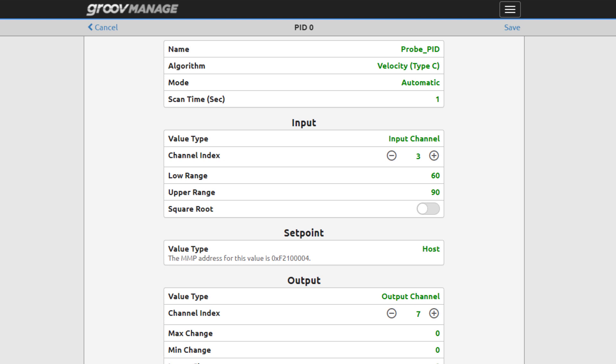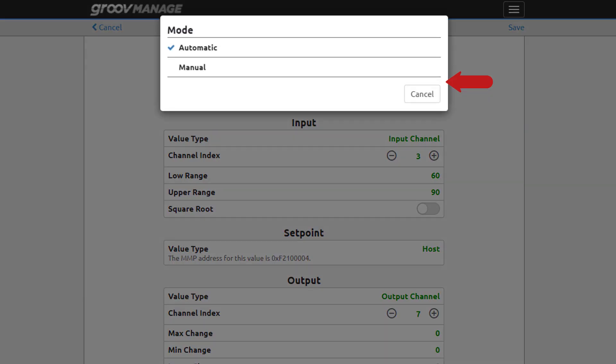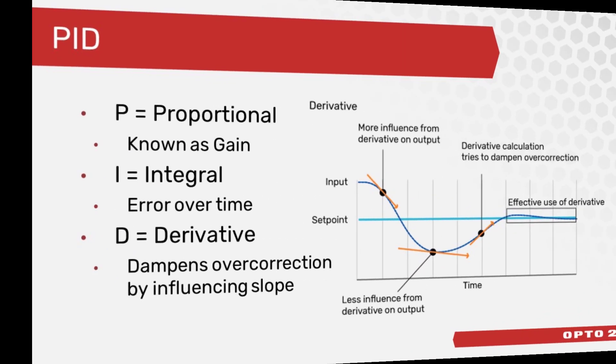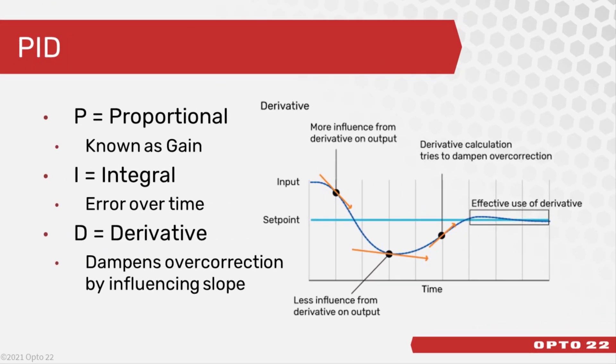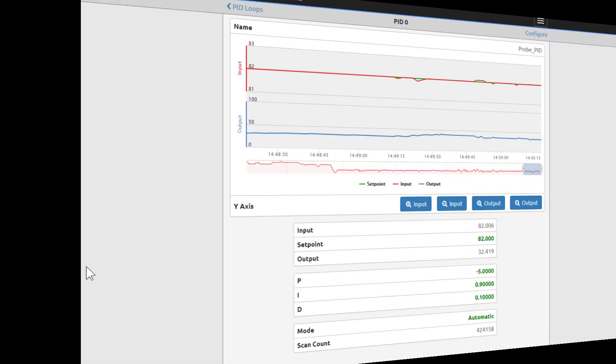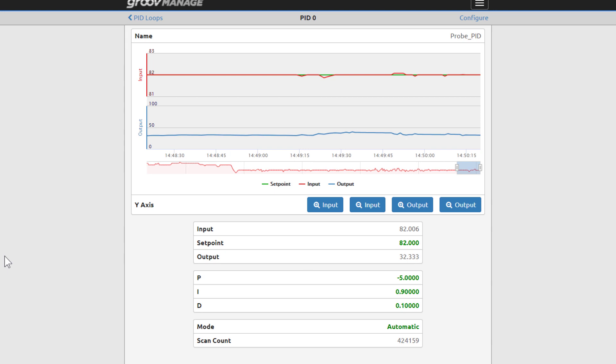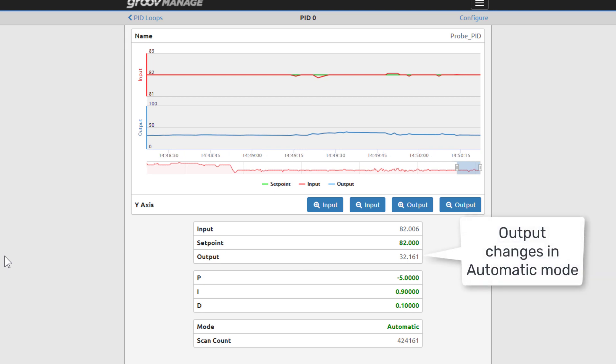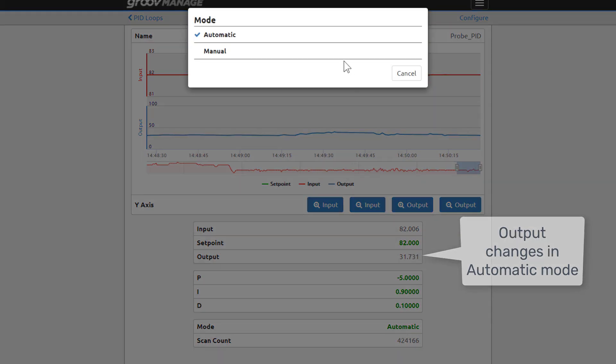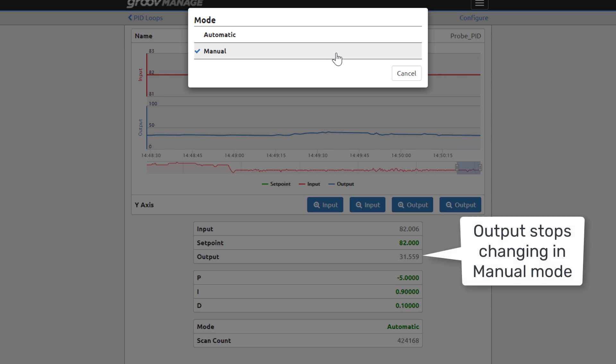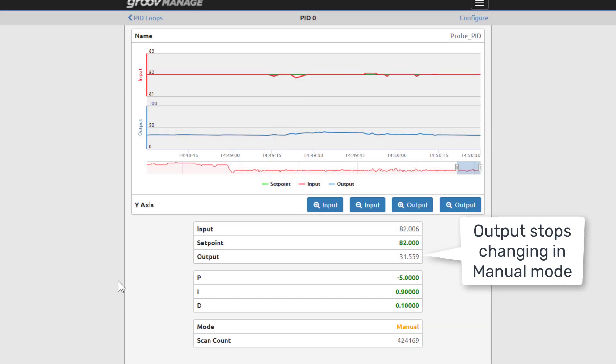PIDs have two modes: manual or automatic. Typically they're set up to be automatic so that they start up automatically. A PID in automatic mode means it'll make calculations based on the difference between the input and set point and change the output to drive the input towards the set point. Manual mode means the PID stops making changes to the output, but it keeps writing the output to the configured destination.